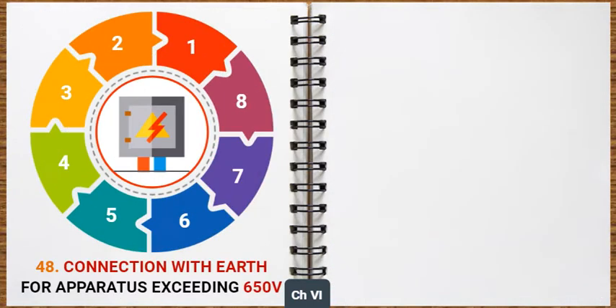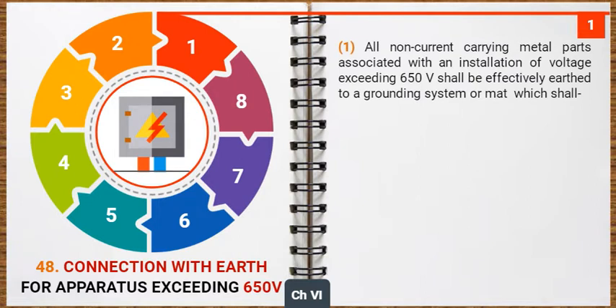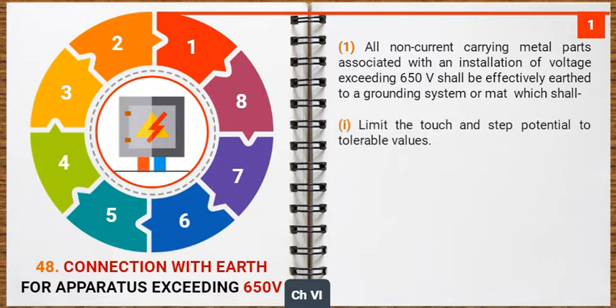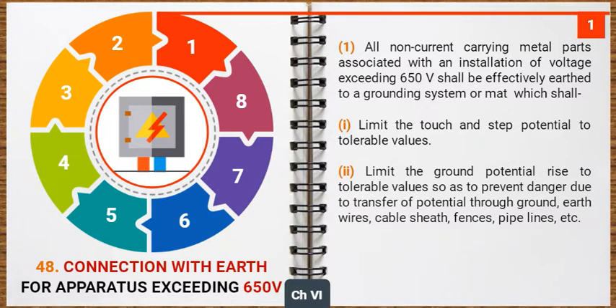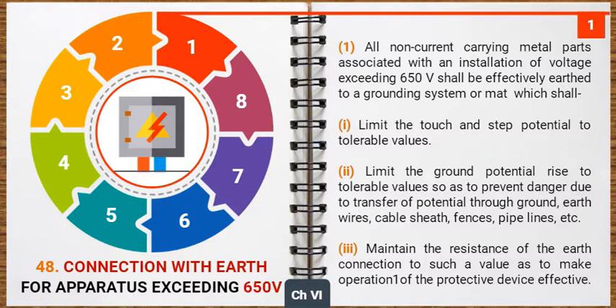Let us look at the safety provisions related to connection with earth for apparatus exceeding 650 volt. All non-current carrying metal parts associated with an installation of voltage exceeding 650 volt shall be effectively earthed to a grounding system or mat which shall limit the touch and step potential to tolerable values, limit the ground potential rise to tolerable values so as to prevent danger due to transfer of potential through ground, earth wires, cable sheath, fences, pipelines, etc. Maintain the resistance of the earth connection to such a value as to make operation of the protective device effective.